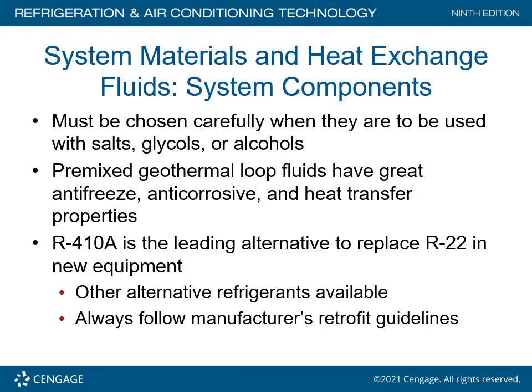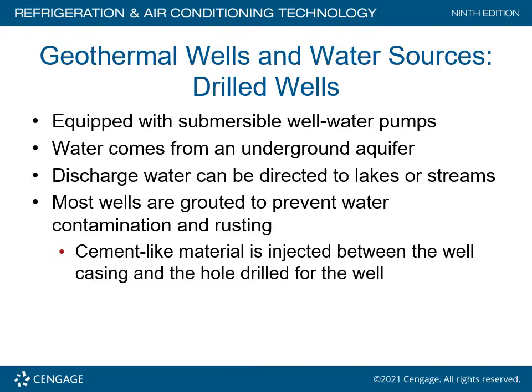System components must be chosen carefully when used with salts, glycols, and alcohols. Pre-mixed geothermal loop fluids have good antifreeze, anti-corrosive, and heat transfer properties. R-410A is currently the industry standard refrigerant, replacing R-22 in new equipment. Other alternative refrigerants are available, and you should always follow the manufacturer's retrofit guidelines.